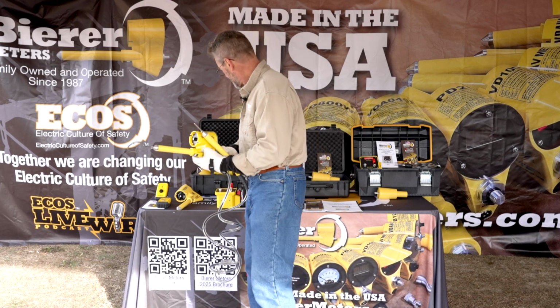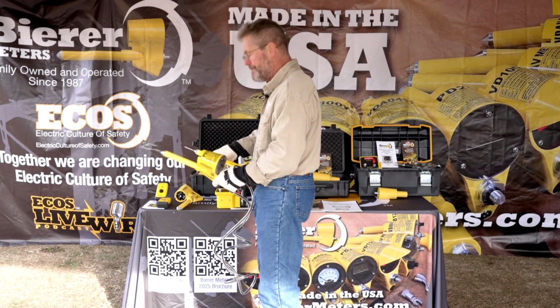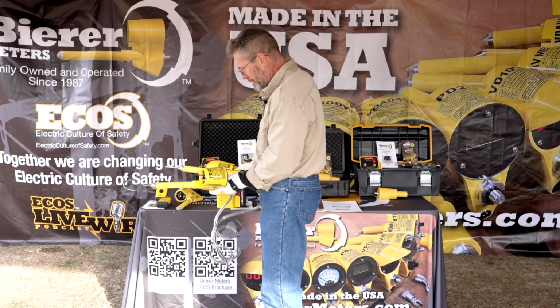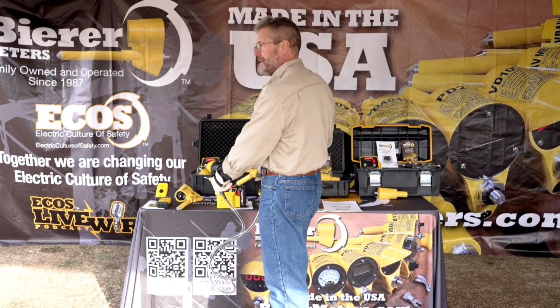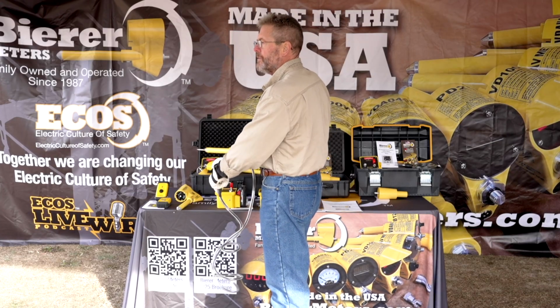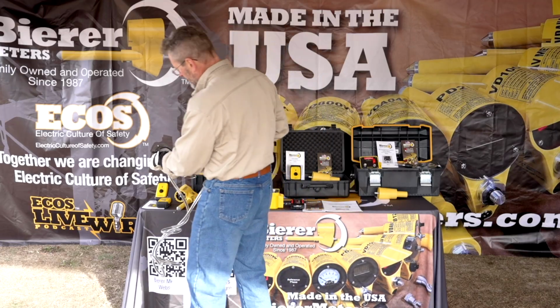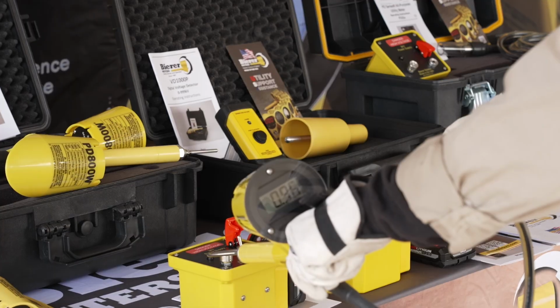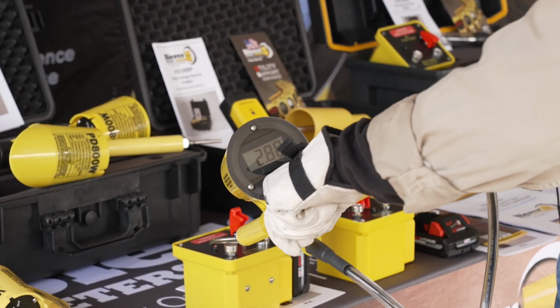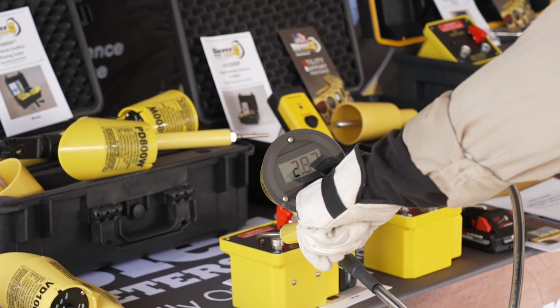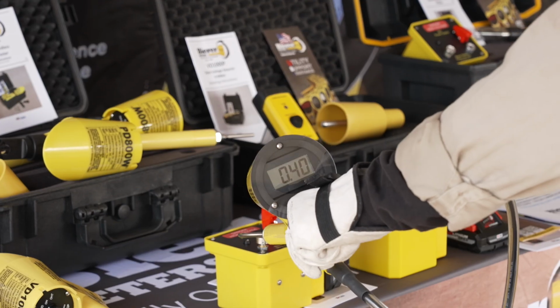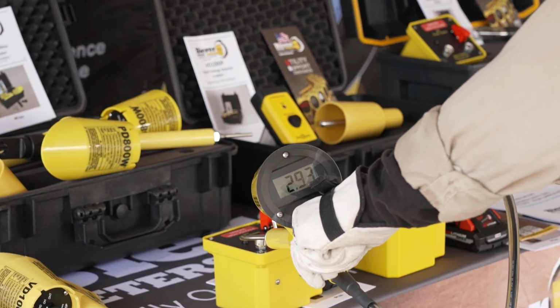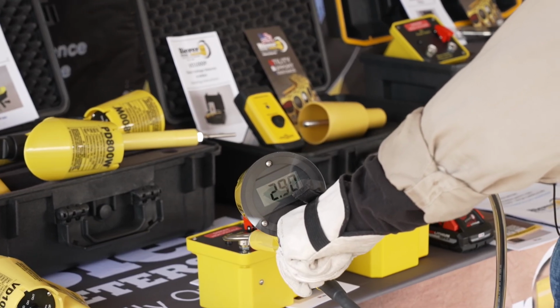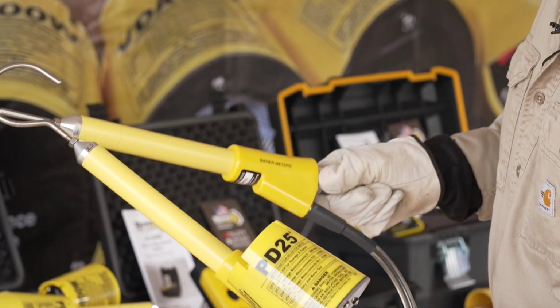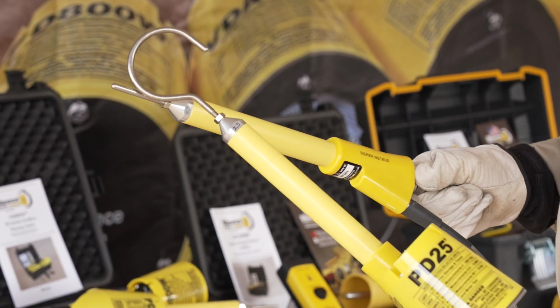And we're going to go. It doesn't matter if you have the meter on the plunger, the hot phase, or the ground. Either way. So we've got, and I like to test, so close to 3,000 volts. And notice how I'm testing using the accessories on the cone tip. Got a hook probe, and we have a straight probe.